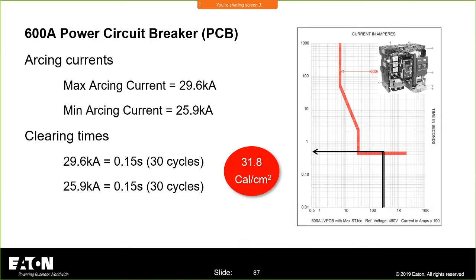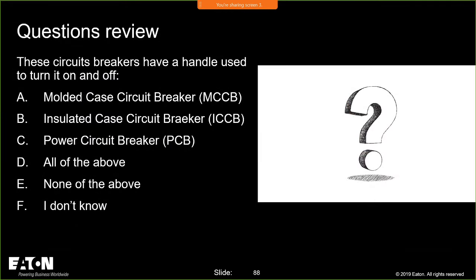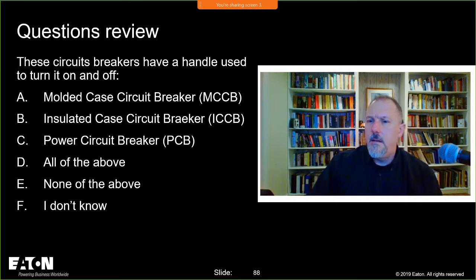This is a 30 cycle delay, 31.8 calories. If I did not do the proper maintenance on my equipment, then I could add time to the clearing, which will increase the electrical hazard. It'll increase the impact of that hazard, the magnitude of the event. It's all about time, clearing time, and current.